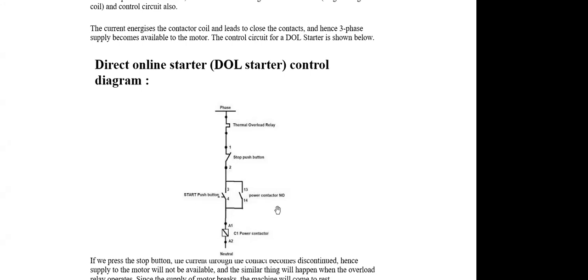In case the motor is taking high current, the thermal overload relay, again, remember this thermal overload setting is very important. Generally, we set 1.2 times the full load current. You can set 1.1 also, depending on the application. And if this thermal overload relay operates, that means the motor is getting overloaded, then this opens up, same theory. This contact is de-energized and the motor stops.